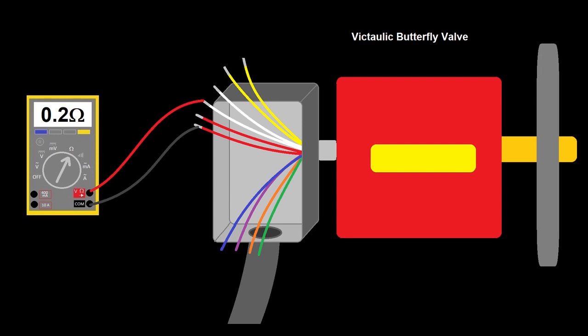When you identify your common and normally open pairs, those are the wires you want to use. They're open when the valve is open and shorted when the valve is closed. In this case, red is our common and white is normally open. I should also note that while you're working on a brand new building, make sure you know the state of the sprinkler system before you start opening valves. You're not going to hurt anything by closing a valve that's open, but don't open any valves that are closed without permission from the sprinkler fitter. They may have some pipes open down the line. You can also determine this by whether or not the pressure gauges are showing zero, but if you're not sure, don't open a closed valve.